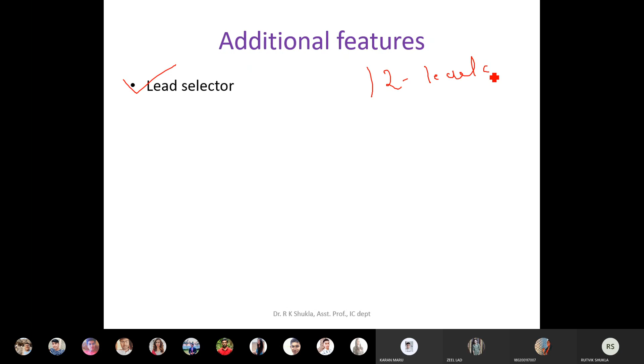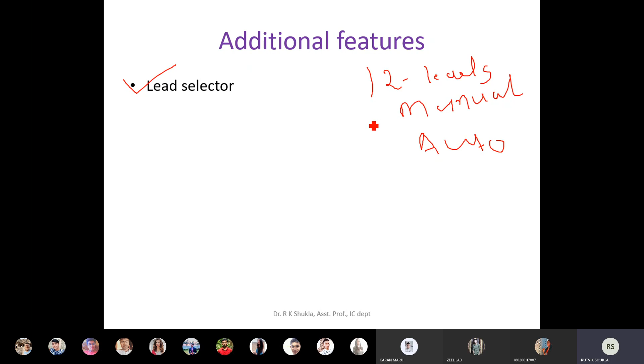So while we were looking at those machines, we saw in the early lectures that there was a BPL machine. In that machine, either you can put a switch on a particular lead, or you can allow all the leads to be scanned at a particular interval. So if you want to view all twelve leads for, say, 10 seconds each, you just have to put it on auto mode. Then the machine will decide that it has to scan each and every lead for that particular duration. So there are two possibilities. Either you can select that particular lead manually, or you can put it in auto mode.